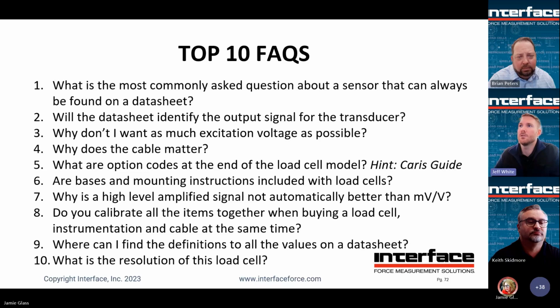Number 7, why is a high-level amplified signal not automatically better than millivolt per volt? Well, millivolt per volt is what inherently comes out of the load cell. When you are amplifying a signal, you are introducing another possible source of error. It's just as if you were adding a mechanical joint in your load string. We don't always know how well the amplified signal will respond to temperature. As the load cells are compensated for that, the amplified signal may or may not be. So sometimes you're going to want that so that you can see a finer resolution, but inherently millivolt per volt will be best.